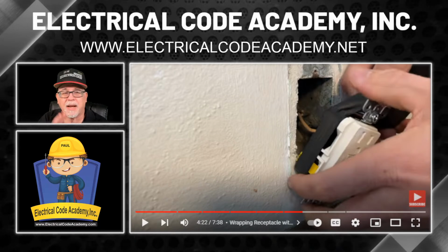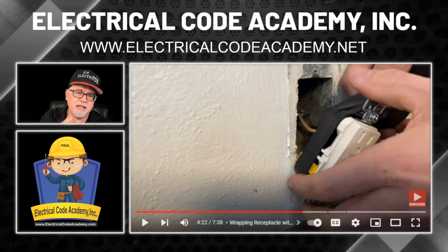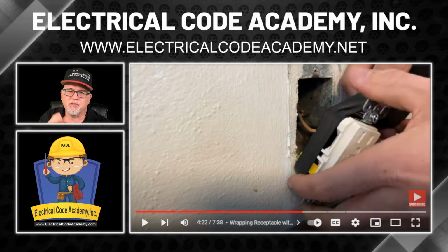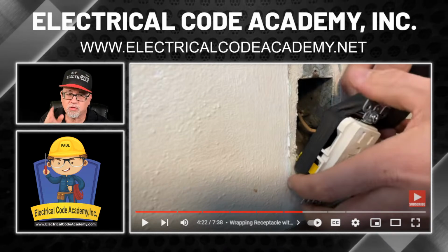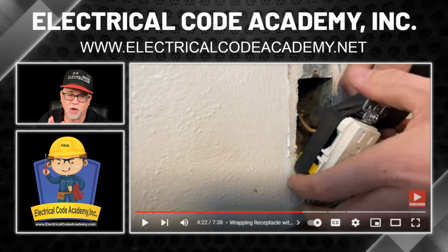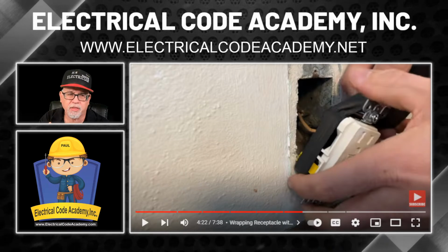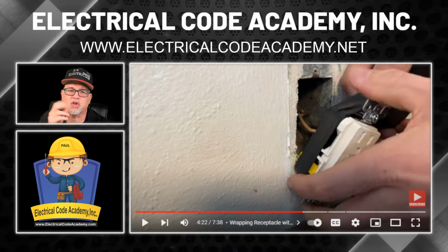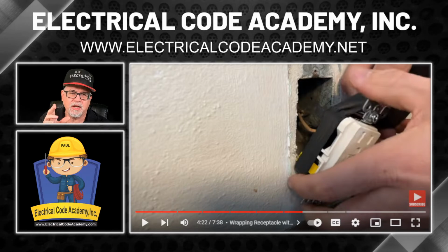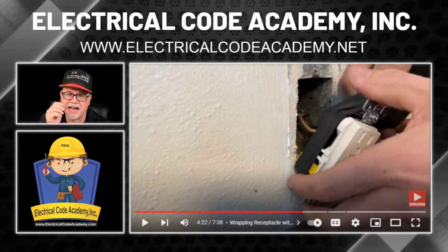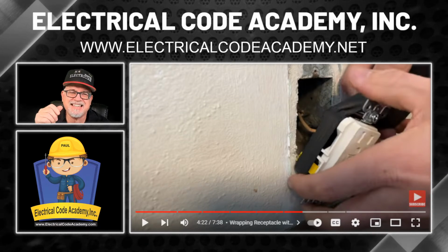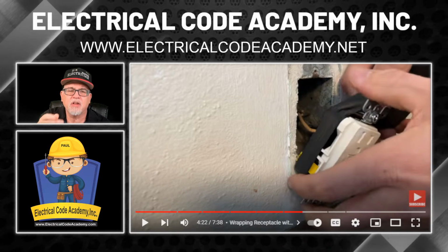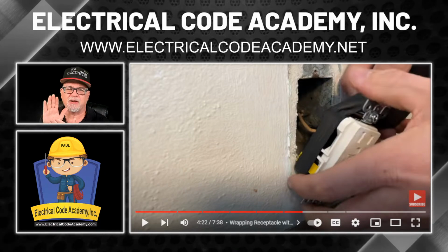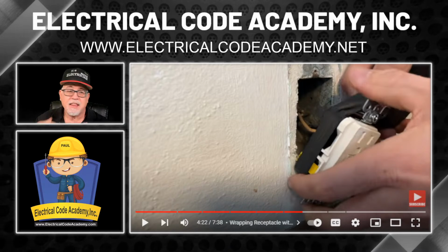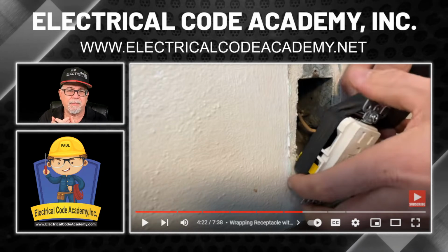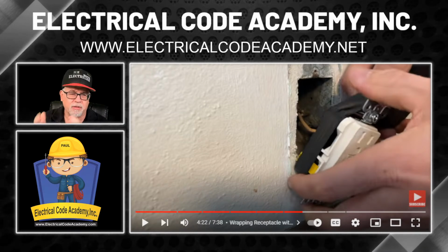Okay. Now, I'll also remind you, see how close he is to this wall with this device? And there's a lot of movement on those conductors. If this is one of the houses like I used to work in that was the old knob or the old cloth, it would start to brittle and crack with even those movements. So once I take that first device off, I usually would splice on pigtails and then neatly get those conductors back so that all I'm working with is those fresh conductors. It only takes a second. That's just me, because usually what happened, it was nothing about the terminals touching a metal box.